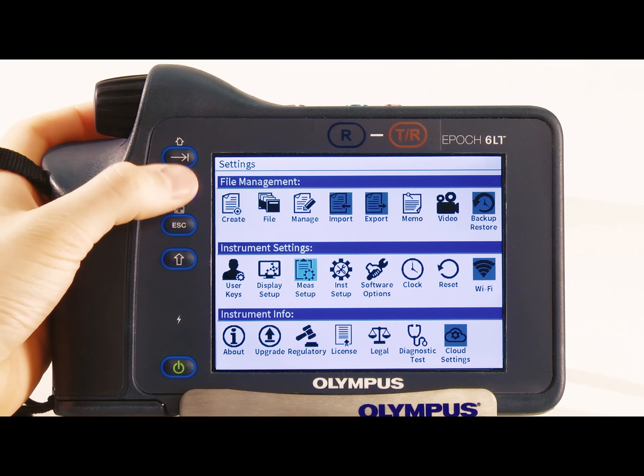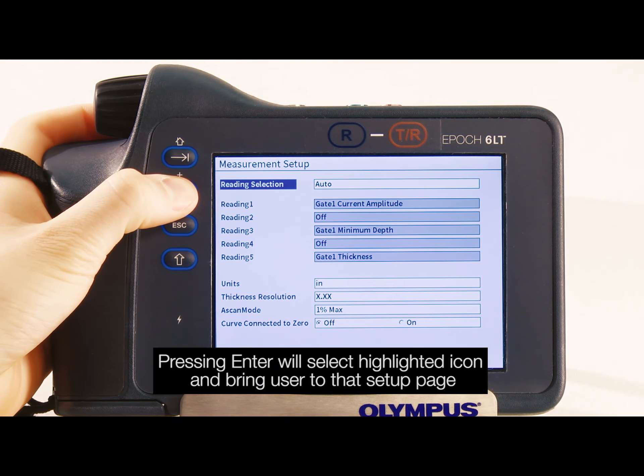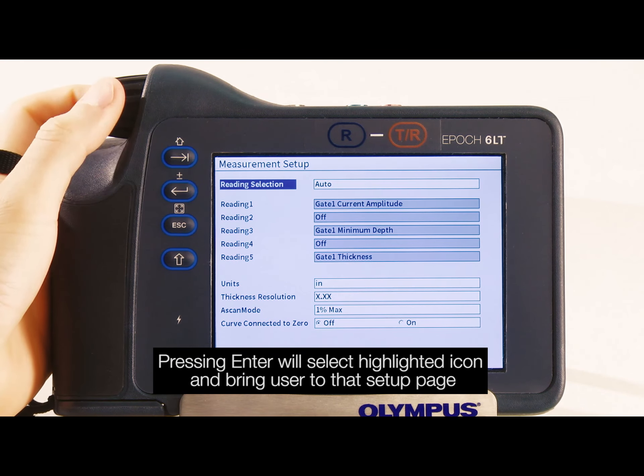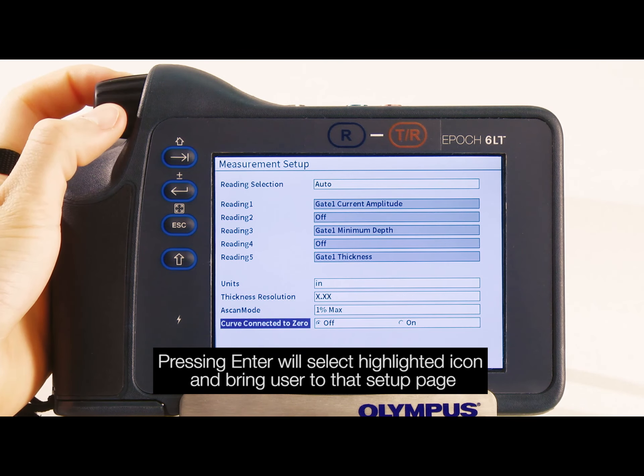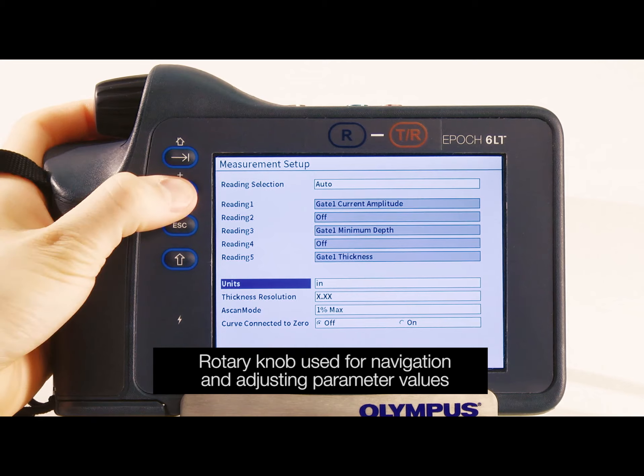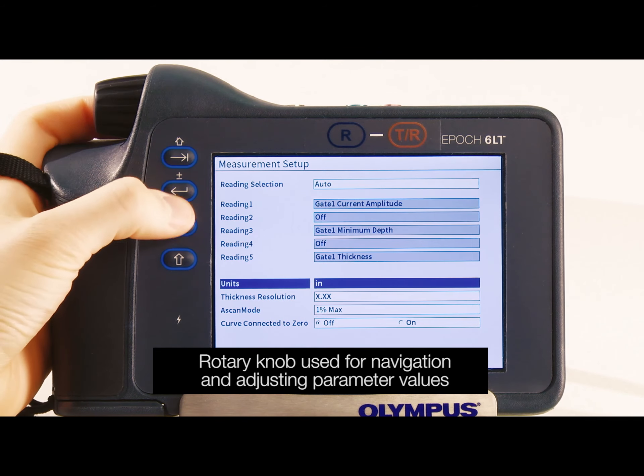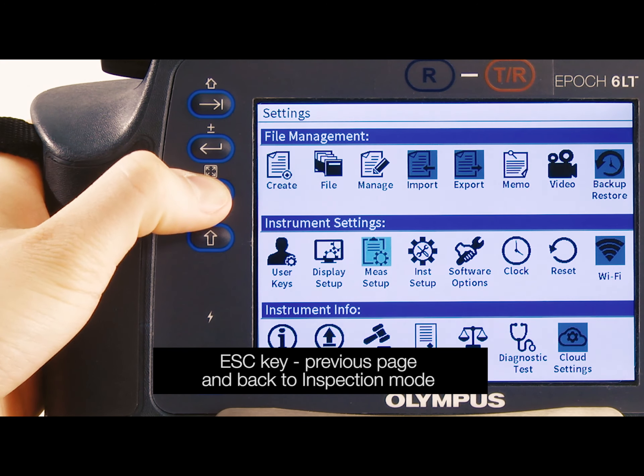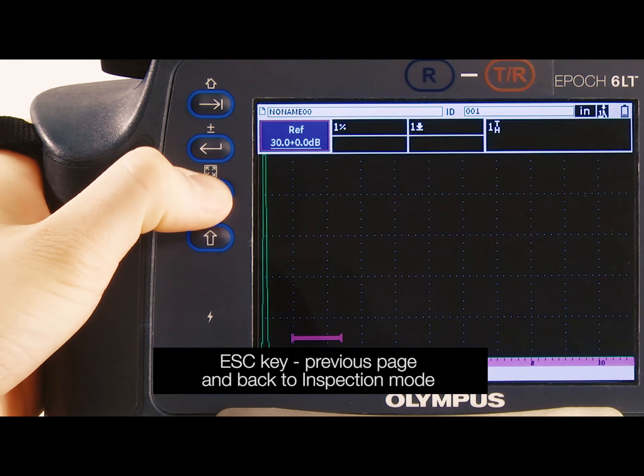While in the settings menu, pressing enter will select the highlighted icon and bring the user to that setup page. The rotary knob is used for navigation as well as for adjusting parameter values. The escape key brings the user to the previous page and eventually to inspection mode.